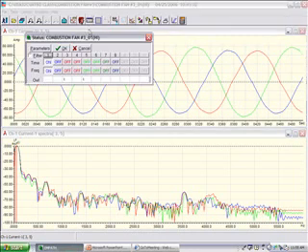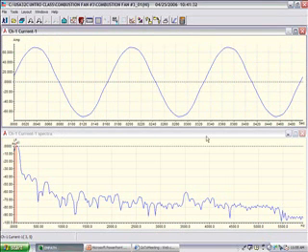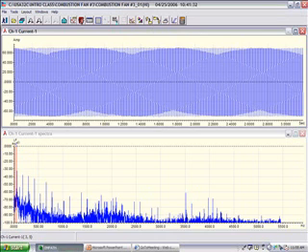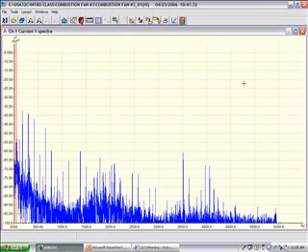High frequency data. If you're doing electrical signature as well, it's nice to see 3 waveforms just to know what things look like. And these are the 3 voltage waveforms across 0.05 seconds. If your software allows, you want to get rid of that for doing analysis. You only want to look at one phase. Okay, let's drop that out.